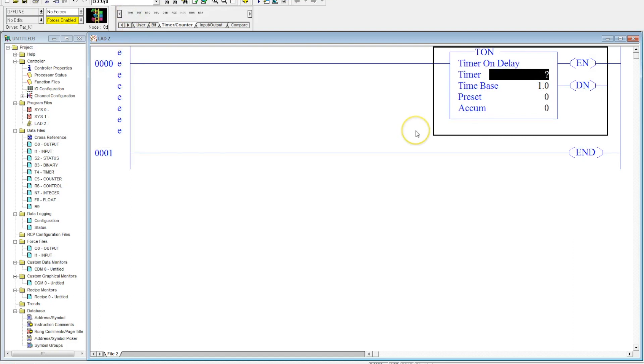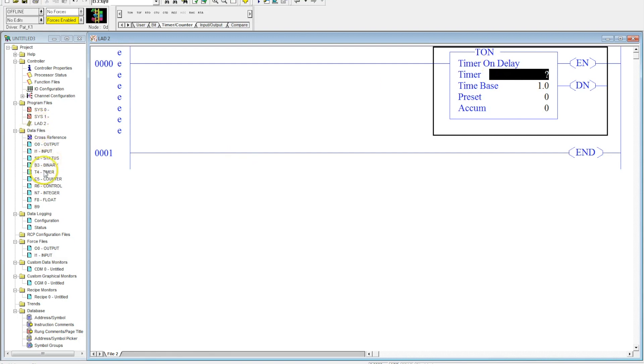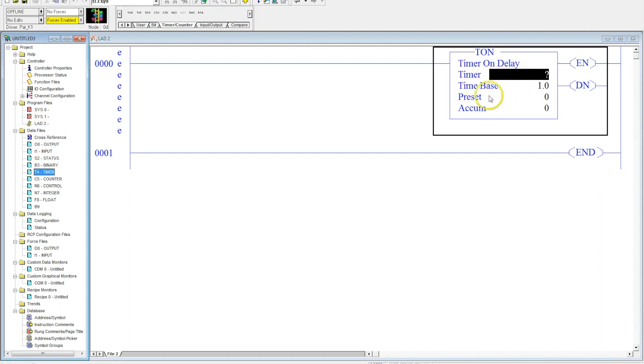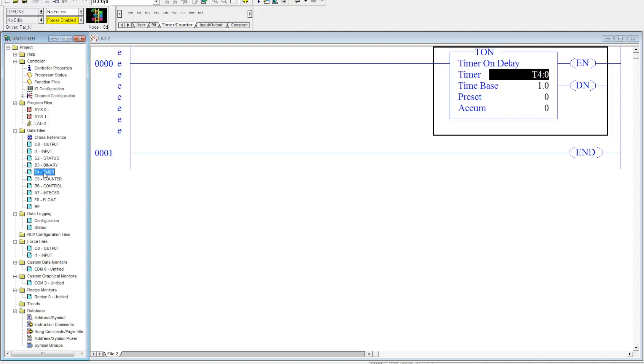We'll add this into a rung and let's go through a little bit about what this is. The first thing we have to do is address it. 99% of the time, timers are going to be located in your data table file four. So that address always has to come up as being T4:0.